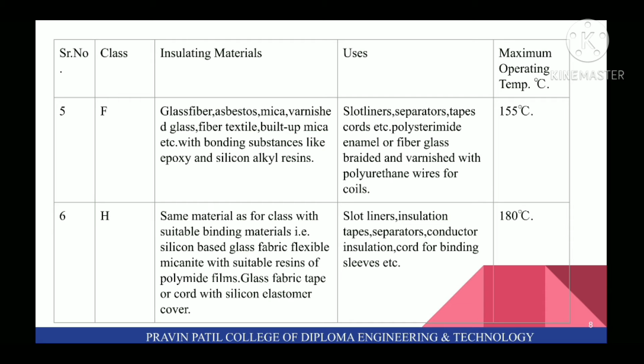For class H insulation, insulating materials are the same materials as for class F with suitable binding materials, that is silicone based glass fabric, flexible micanite with suitable resins of polyimide films, glass fabric tape or cord with silicone elastomer cover. Uses are slot liners, insulation tapes, separators, conductor insulation, cord for binding sleeves, etc. And maximum operating temperature is 180 degrees Celsius.